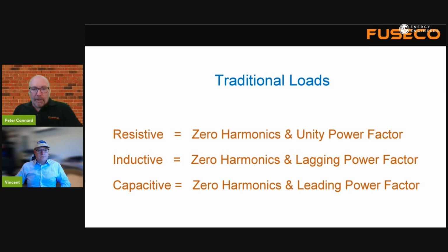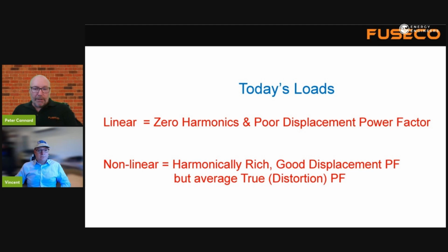We're going to go into more detail on these shortly, but let me briefly introduce these terms. Linear loads are what we typically see in industry today. These have zero harmonics, which we'll also talk about, but can have poor power factor, which can lead to increased costs when we pay our distributor each quarter. We also have lots of non-linear loads, increasing quite a lot over the last 20 to 30 years, due to increased use of variable speed drives and other rectifier-based systems. These cause harmonics, but also poor true power factor, which we'll go into detail about shortly.